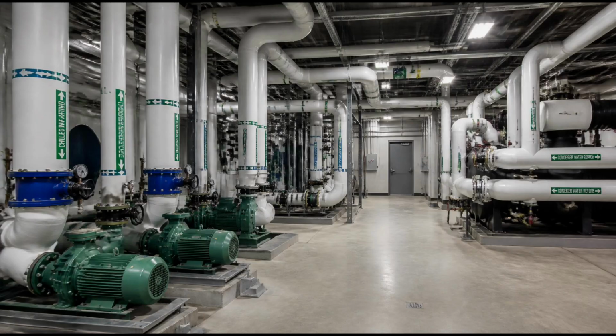Building controls help everything work together. The building automation system coordinates all of these zone-level adjustments and ensures that they make sense in the context of the broader system. If several zones simultaneously call for more cooling, the system increases chilled water flow and adjusts the air handler output to meet the aggregate demand.